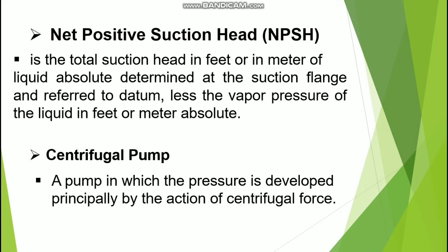Then net positive suction head or NPSH, it is the total suction head in feet or in meter of liquid absolute determined at the suction flange and referred to datum, less the vapor pressure of the liquid in feet or meter absolute. Then let's proceed to centrifugal pump. So centrifugal pump, it is a pump in which the pressure is developed principally by the action of centrifugal force.